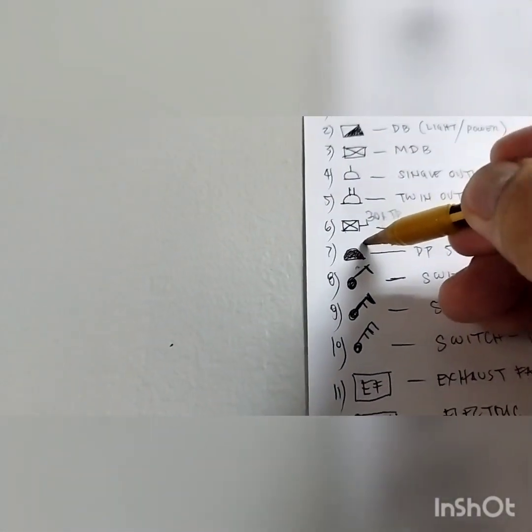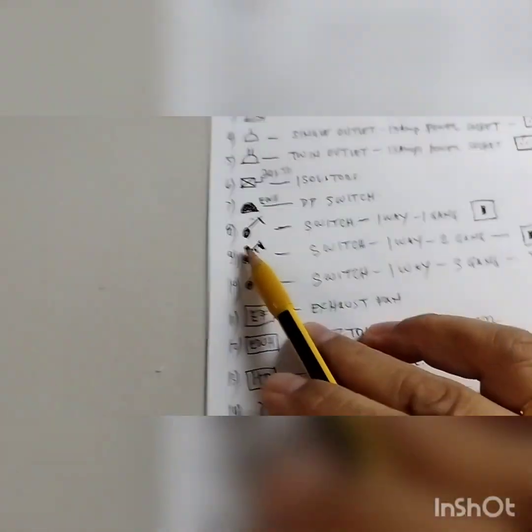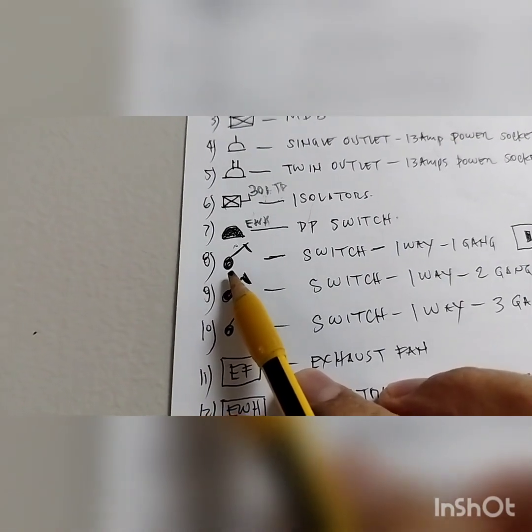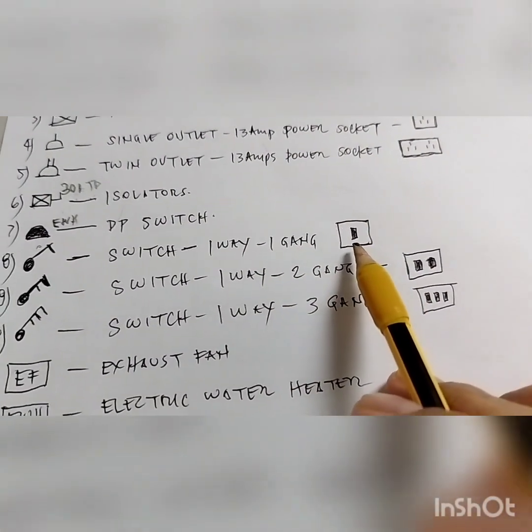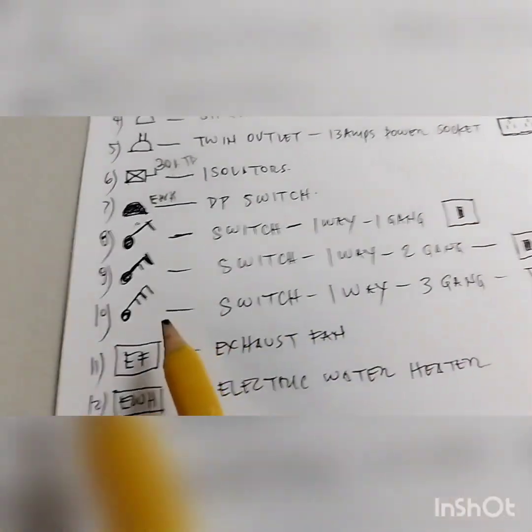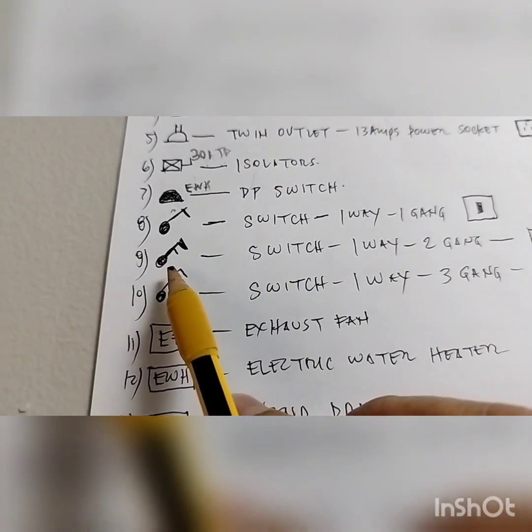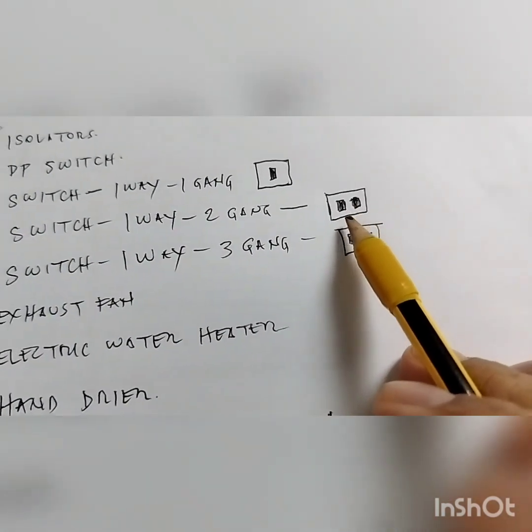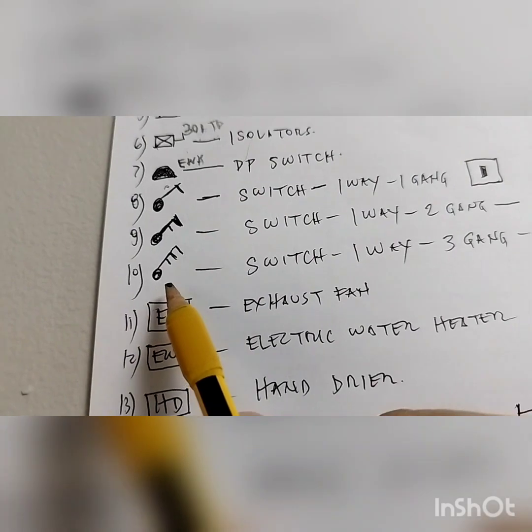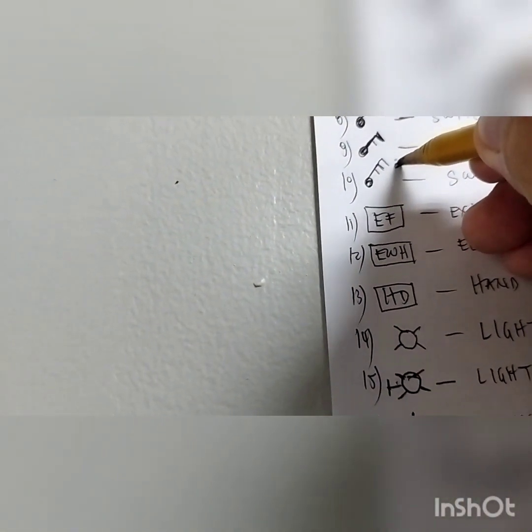They will put additional symbols — for example, this marking here means that is a DP switch for an electric water heater. This symbol is for a switch: this one is a switch one-way one-gang. If you see it, it's like this — one switch only in one plate. This symbol is a two-gang switch, switch one-way two-gang — you will see two switches in one plate. Then this symbol is switch one-way three-gang.